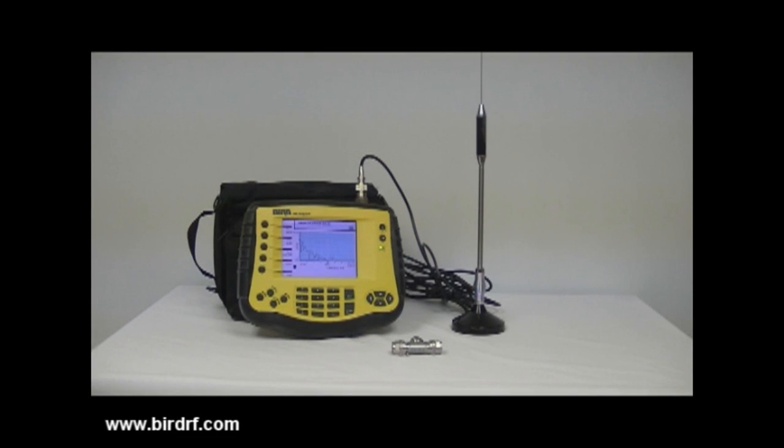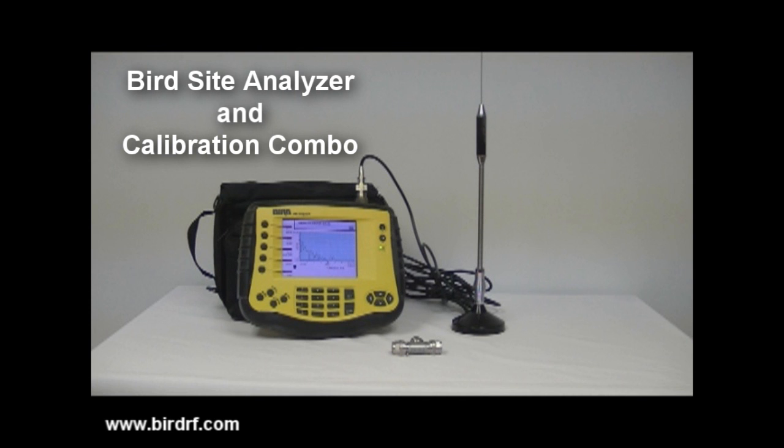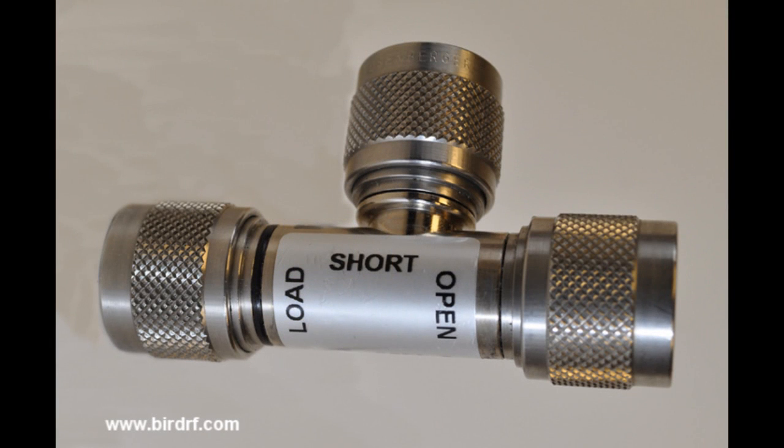To complete the calibration you will need a Bird Site Analyzer and a calibration combo which contains open, short, and load elements.